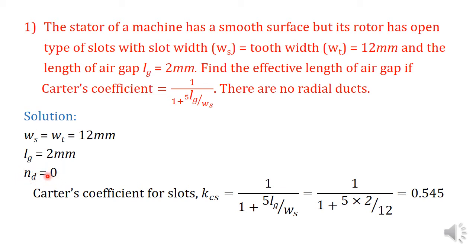We need not consider the case of ventilating ducts. In order to find the effective length of air gap, we have to calculate the gap contraction factor. For finding the gap contraction factor, we have to find the Carter's coefficient for slots, because here there are only slots and no ducts. The Carter's coefficient for slots, as given in the question, is 1 by (1 plus 5 LG by WS), which equals 0.545.